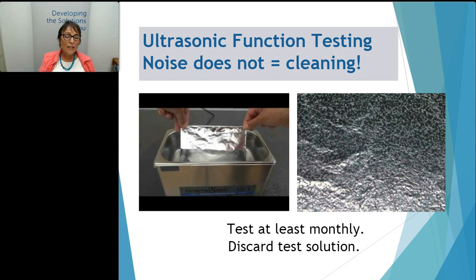Aluminum foil has been a tried and true method for years. If you do foil testing, don't use that as your cleaning solution—discard the water or whatever was in there, because you'll have particles of aluminum foil in that test solution. Do this probably at least monthly, or check your ultrasonic operating instructions for how often they recommend function testing. The aluminum foil pattern should be an even overall pattern of dimples and possibly some tiny holes, evenly spread over the entire sheet of foil.